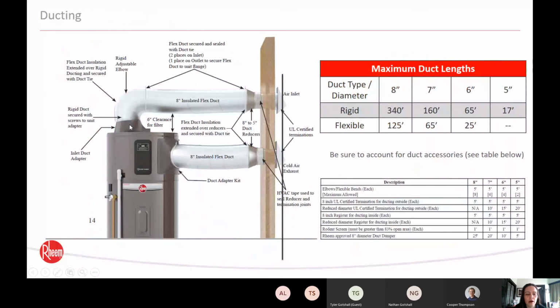So these do come ductable. You do have to purchase these little adapters aftermarket if you need to duct. But you can go, as you can see, all the way up to 340 feet on 8-inch rigid ducting, 125 feet on 8-inch flexible ducting. You do have to take into account if you have any 90 degrees or angles or anything like that. But with that being said, those are pretty nice long lengths. I can't imagine that you wouldn't be able to duct as needed. Only thing to keep in mind, you do need 6 inches above this unit. Remember, we talked about cleaning out that filter. So 6 inches of space to access that filter. And that's really the only clearance that we need on these units.